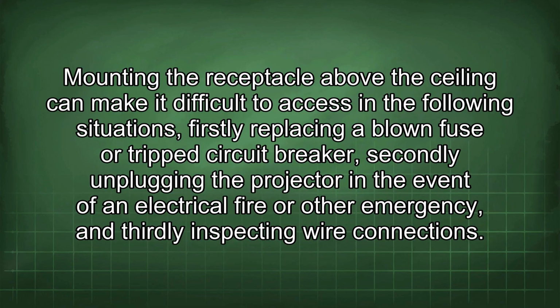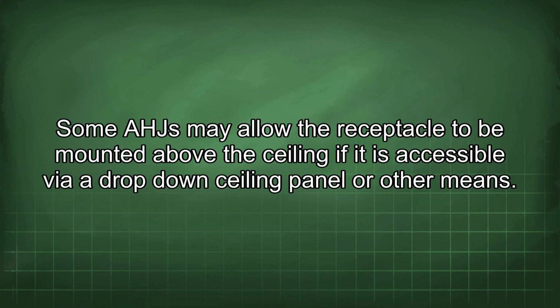Mounting the receptacle above the ceiling can make it difficult to access in the following situations: firstly, replacing a blown fuse or tripped circuit breaker; secondly, unplugging the projector in the event of an electrical fire or other emergency; and thirdly, inspecting wire connections. Some AHJs may allow the receptacle to be mounted above the ceiling if it is accessible via a drop-down ceiling panel or other means.